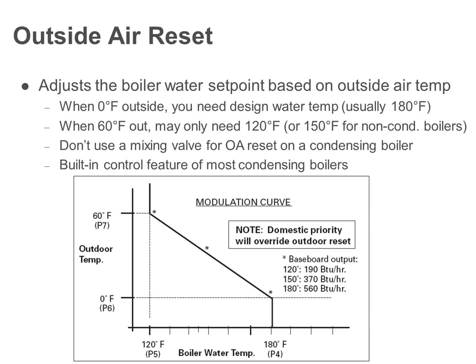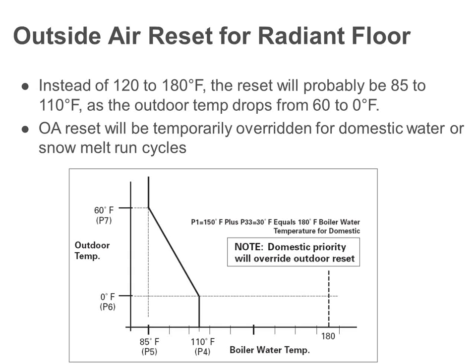That's the name of the game. When you start looking at radiant floor systems, there's no reason you should not have a condensing boiler in a radiant floor system. This is a perfect application. It always likes cooler water. The boiler likes the cooler water. That's what you're doing here.